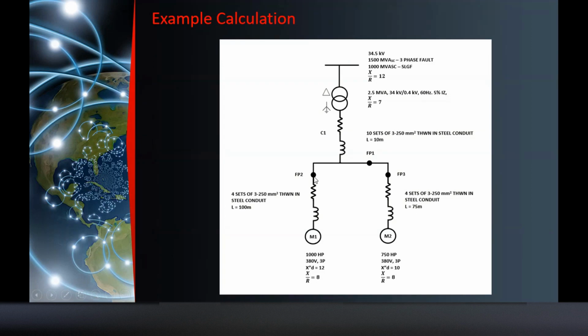So if the breaker they sized up is, let's say, 25 kAIC, all throughout that feeder it is 25 kAIC, for flexibility of the system. They can transfer loads if they add more. That is what others do, so the kAIC rating of the feeders is identical. Okay? So this is the problem, example, calculation.